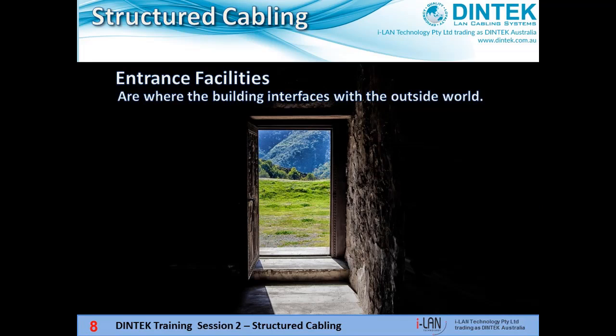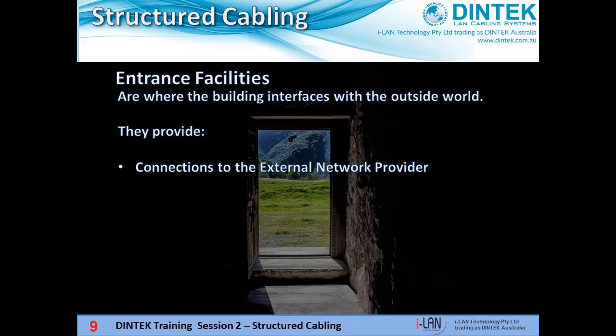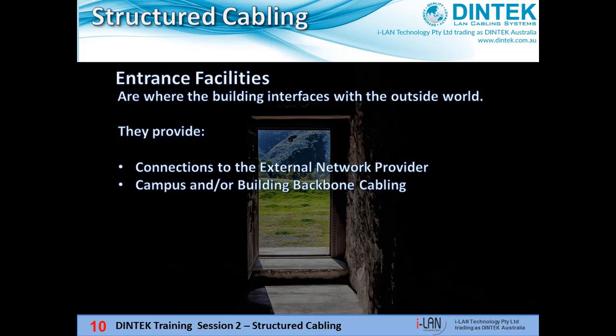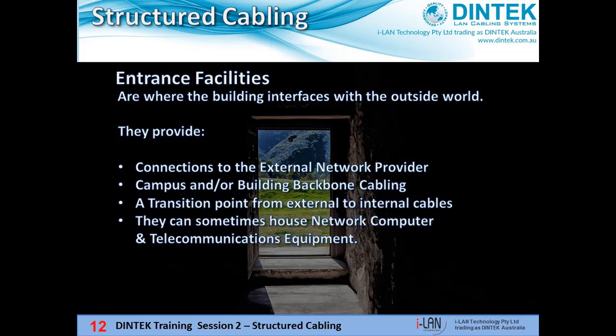They consist of various types of telecommunications cables, including private optic fibre cables and public telephone carrier networks, where they enter a building before continuing on to the equipment rooms — where we'll find our servers, routers, and PABX systems. Entrance facilities provide connections to the external network provider, a termination point for campus and building backbone cabling, a transition point from external to internal cables, and can even sometimes house network and telecommunications equipment.